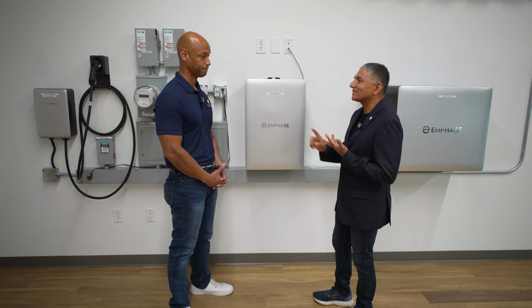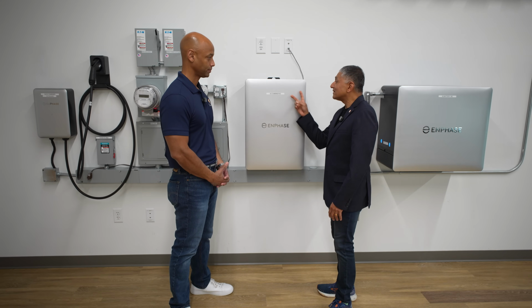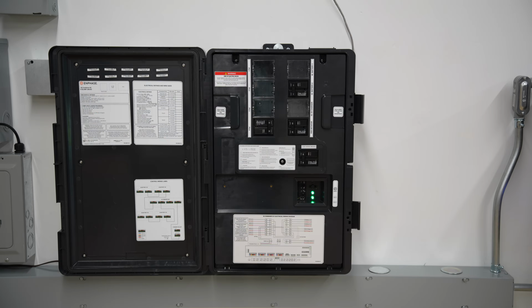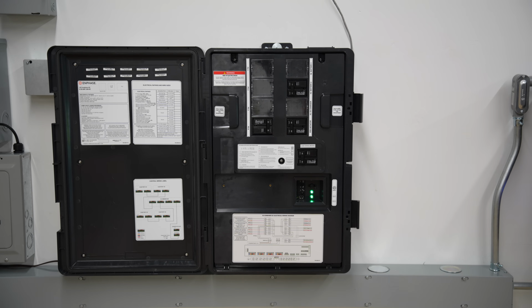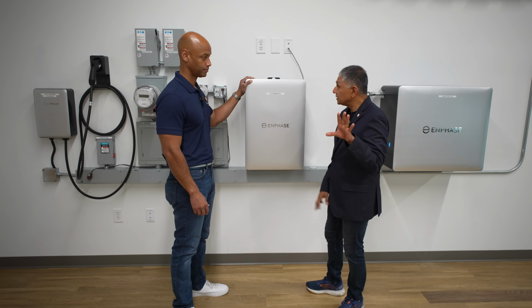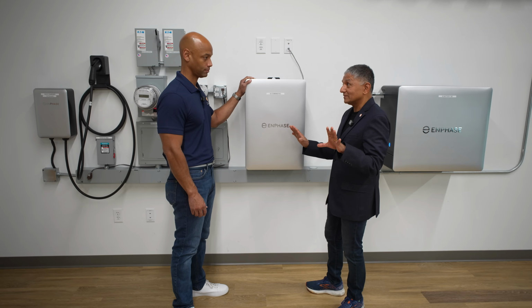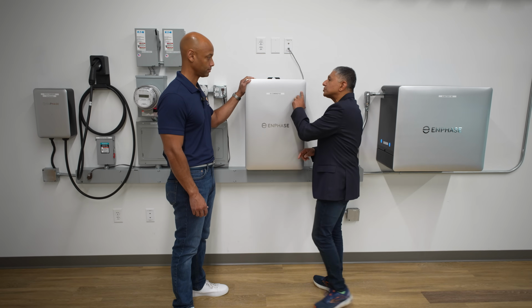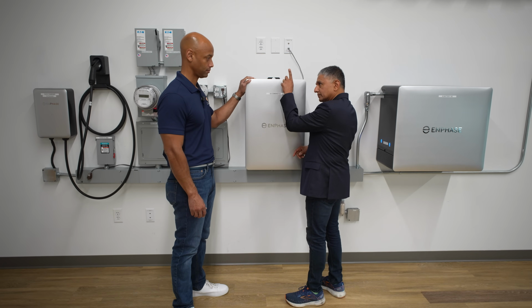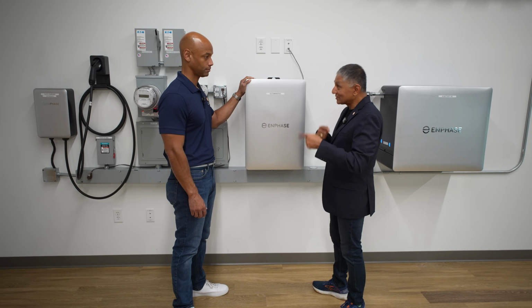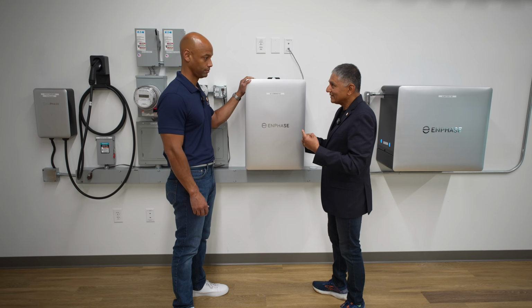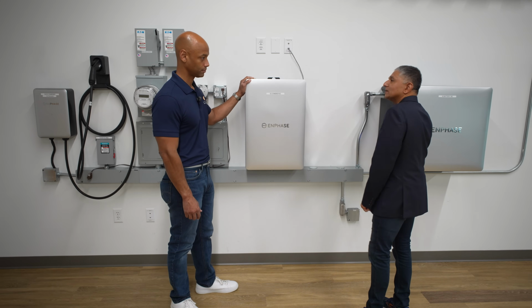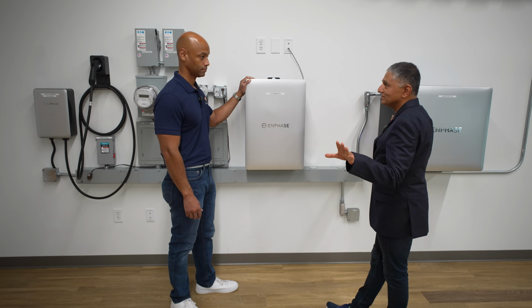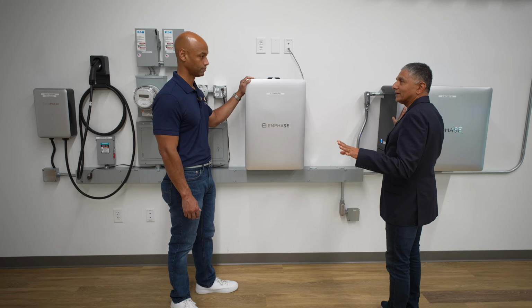Great. There's one more thing that this thing does really, really well. There is a built-in DER relay in here, a 100 amp DER relay. What that 100 amp DER relay allows us to do is, in the event of a black start, and this is, by the way, very unique to Enphase, right? The combination of the IQ8 on the roof that synthesizes its own grid, right? So let's assume for a moment your batteries are completely drained. You're in a multi-day outage, right? Your batteries are completely drained.